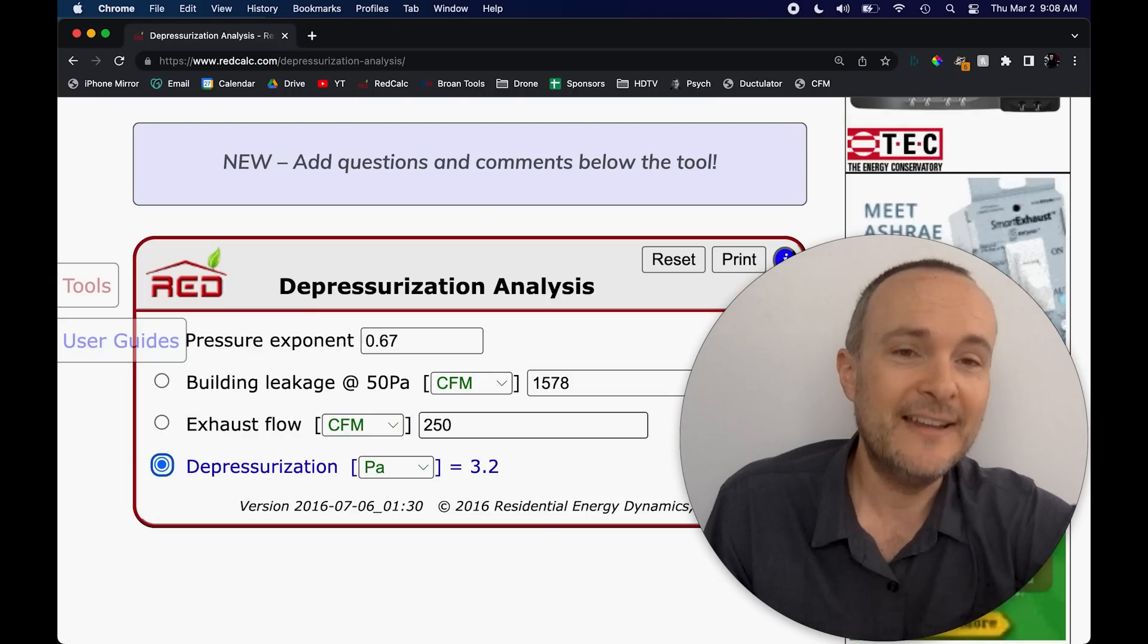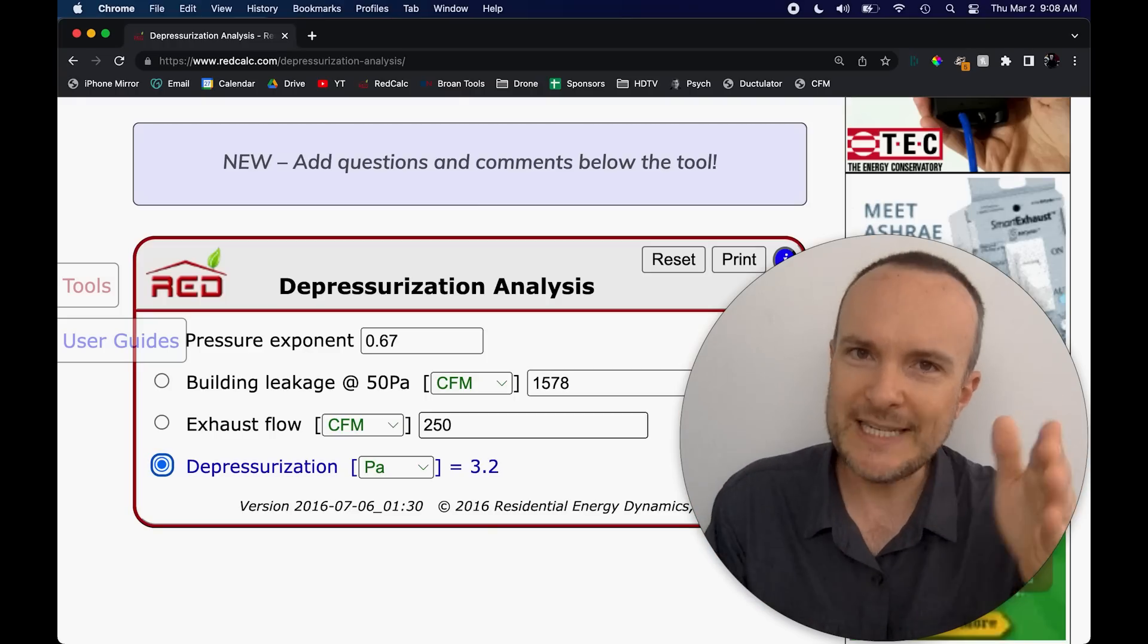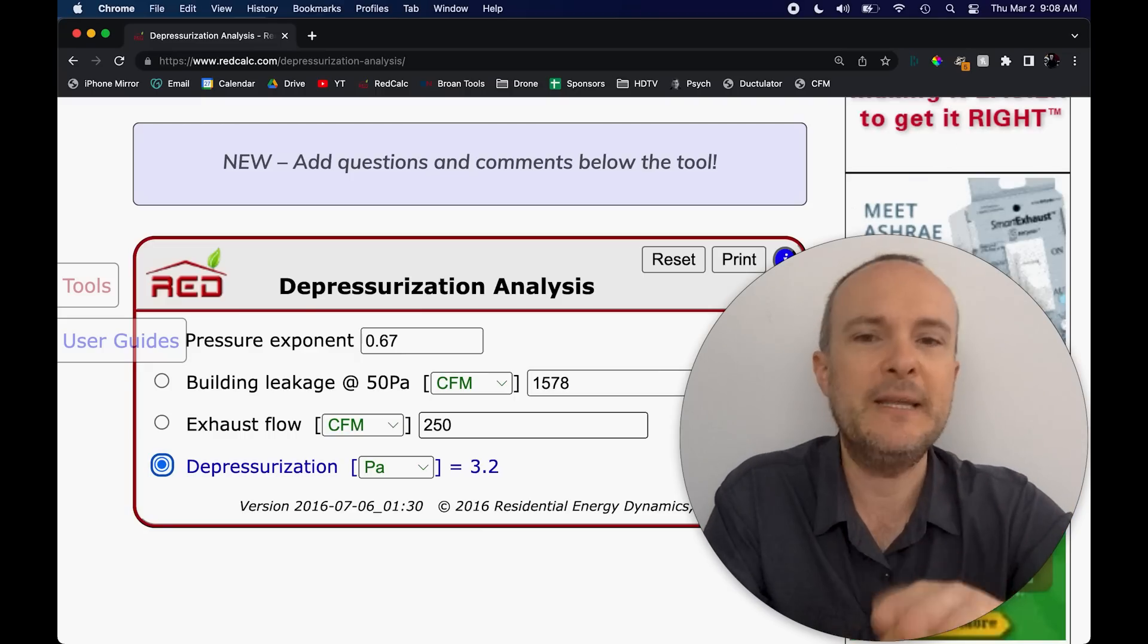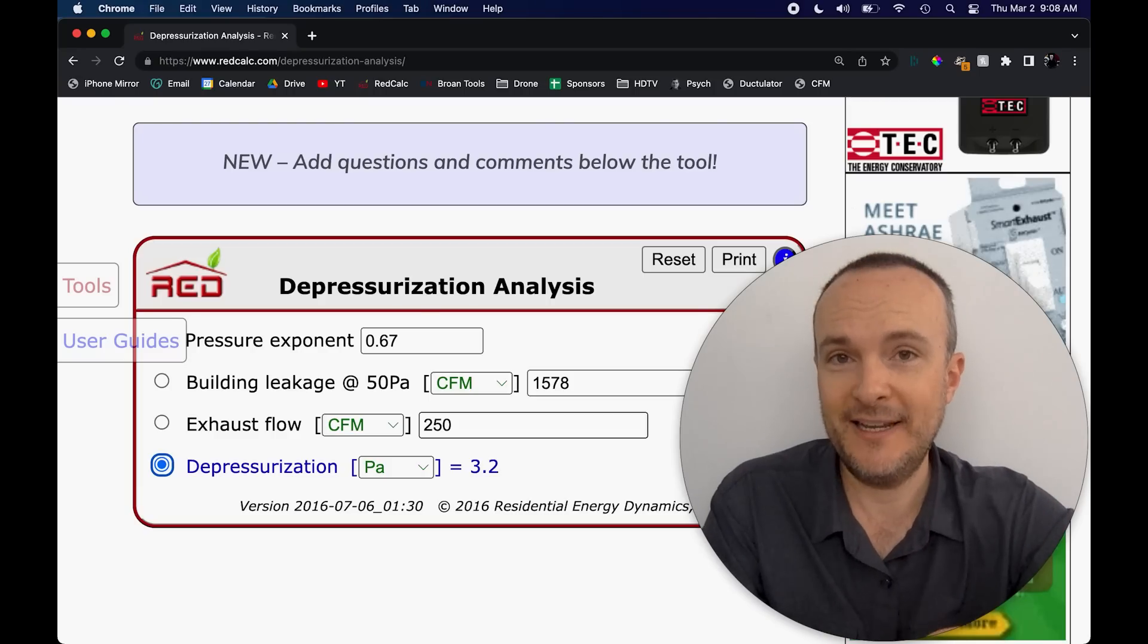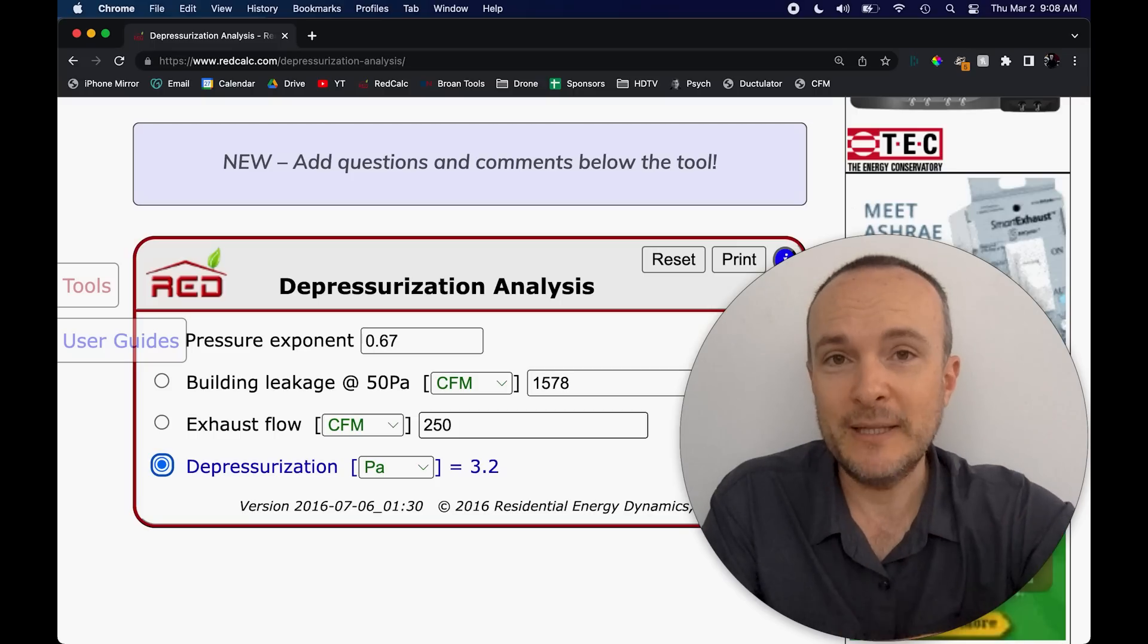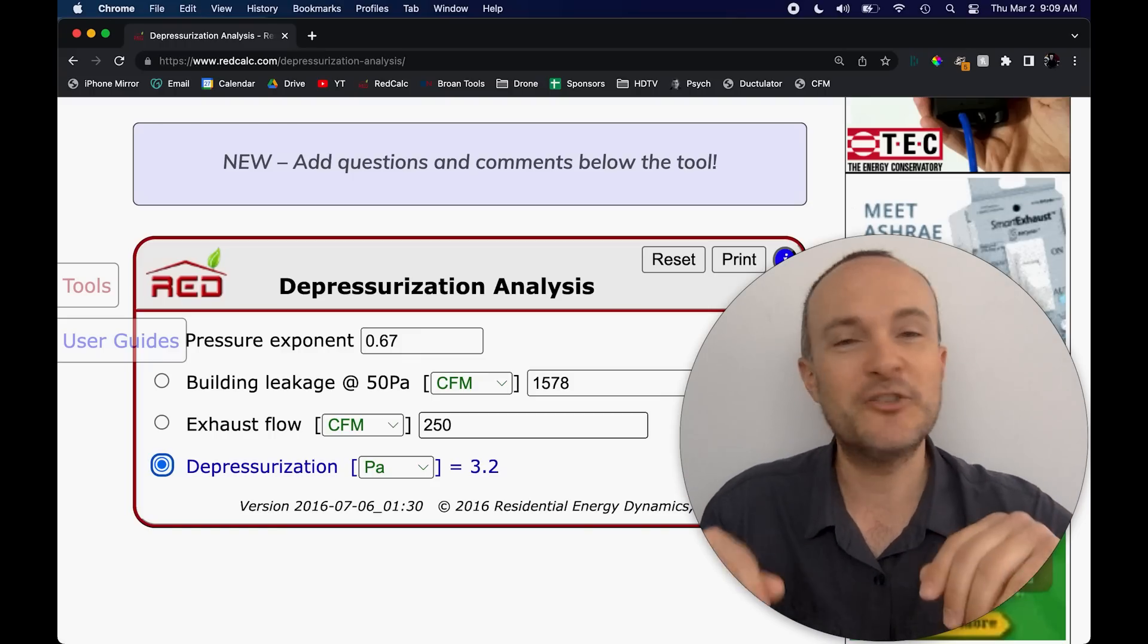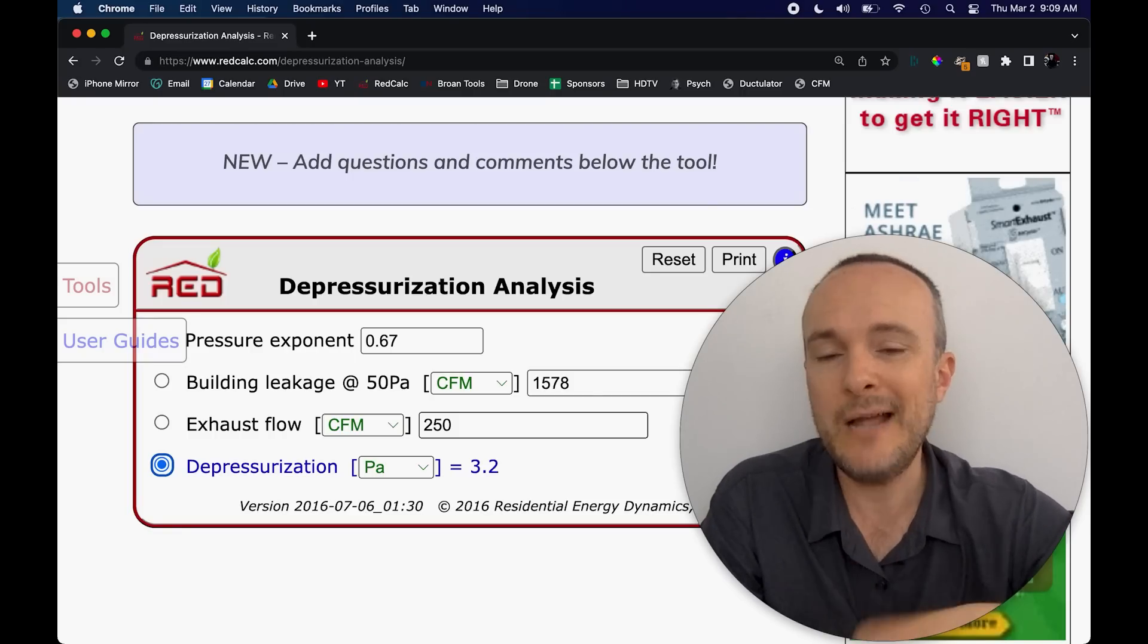If I turn on all five of them at the same time, three Pascals, that is starting to be a problem. Now, at this point, if I build this home to code, to future proof it, to all future codes, so that it's at three air changes per hour, and hopefully it never gets leakier. But if this home ends up being 1578 on the blower door and I turn on all five of my exhaust fans all day long, and I have a wood burning fireplace in here or some kind of other open hearth fireplace, now we have a major problem because that house simply cannot work that way.